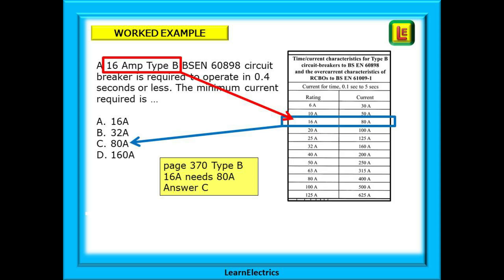Use the information in the question. It tells us it is a 16 amp type B breaker and the time is 0.4 seconds or less. Looking at the table we can find 16 amps and this tells us that the fault current must be at least 80 amps so we should choose answer C. If you are on the right page you will find the right answer.